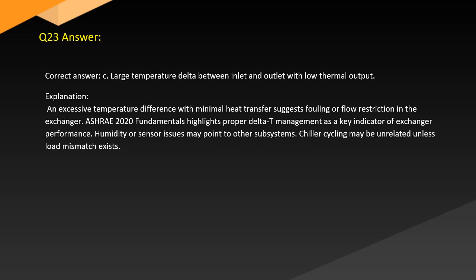Answer. Correct answer: C. Large temperature delta between inlet and outlet with low thermal output. Explanation. An excessive temperature difference with minimal heat transfer suggests fouling or flow restriction in the exchanger. ASHRAE 2020 Fundamentals highlights proper delta T management as a key indicator of exchanger performance. Humidity or sensor issues may point to other subsystems. Chiller cycling may be unrelated unless load mismatch exists.